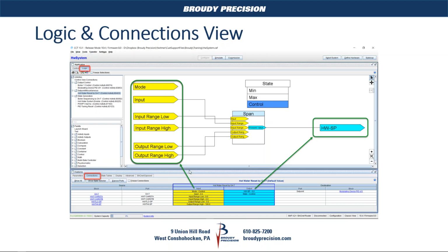So if we're on our logic at the top, you'll see that in this wire sheet space, yellow is input designations, and these are called activity inputs. And you'll see over in this palette, there's activity inputs and activity outputs. These are the slots that you're adding to be able to connect to external or network input, network output points, and physical inputs and outputs. That's where you'll be pulling in the data for the logic to work with.